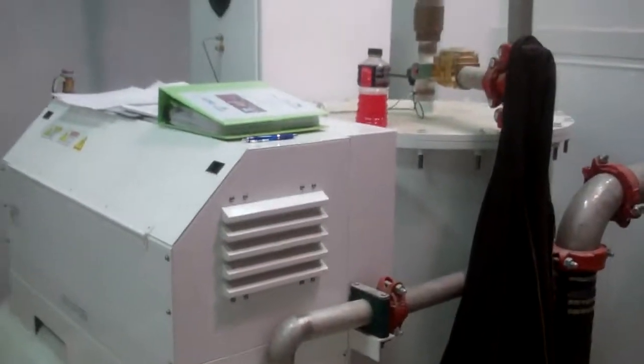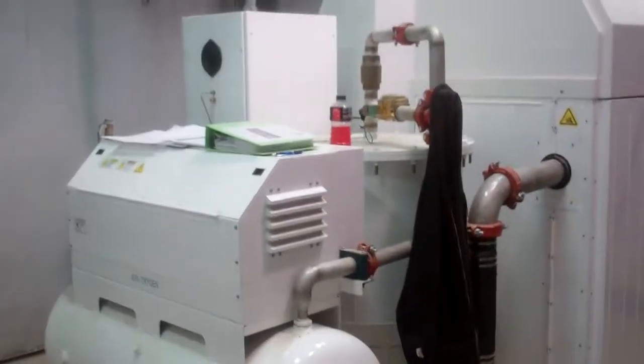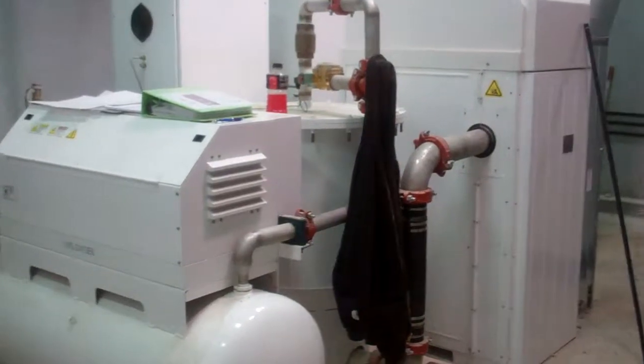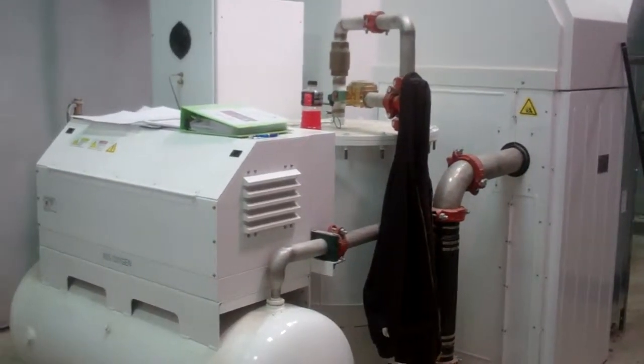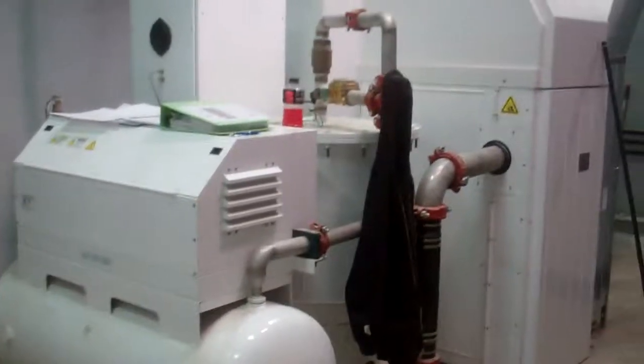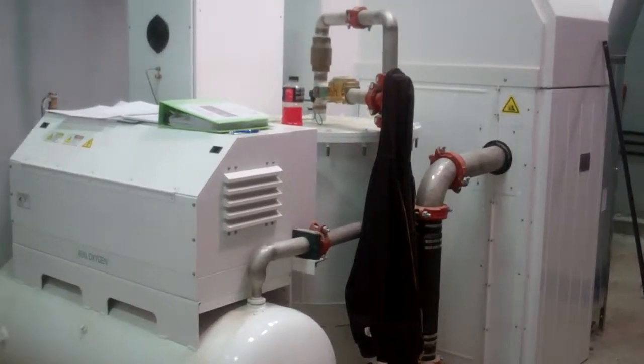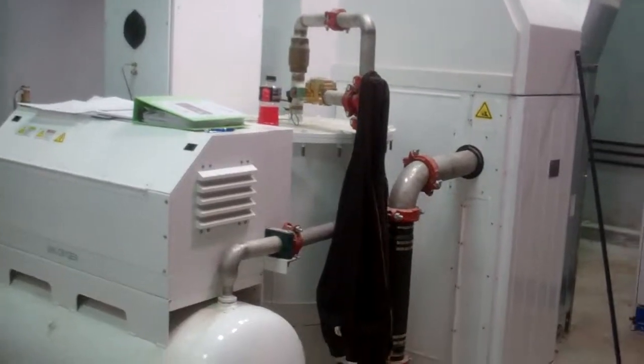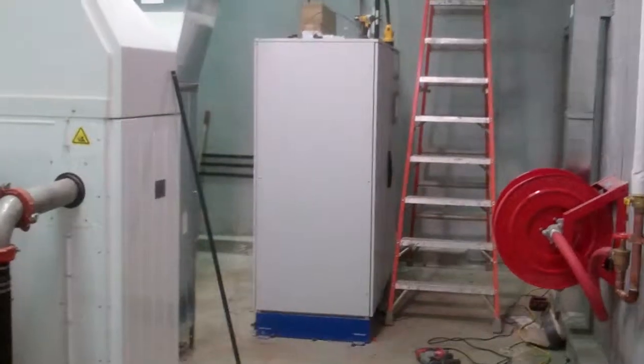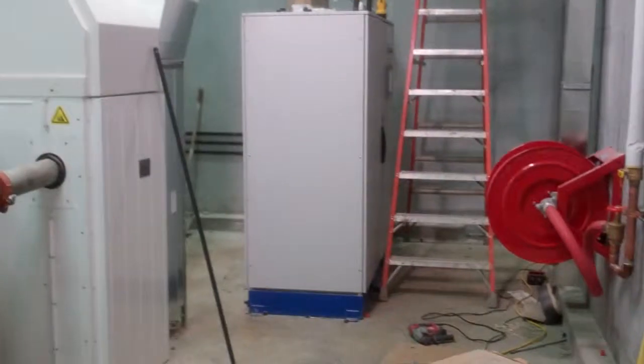This happens to be the redundant DOCS 500 system in the same building and room — basically a standby unit. Both of these DOCS 500s are designed to put out about one ton per day of oxygen at 93% purity. They both feed a Pinnacle 140 pound per day ozone generator, shown here.